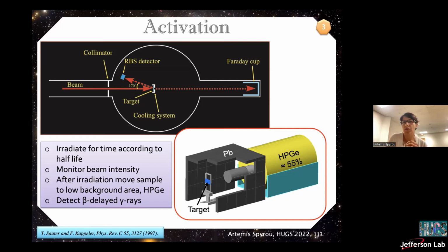And similar for the efficiency of the detector. We need sources that are very well calibrated, you know, the activity, when they were produced, and you need to know the distance from your detector and so on, and you get an efficiency. And again, you will get 2-3 efficiency data points, and everything else is done through a simulation once you validate it. Okay, thank you.